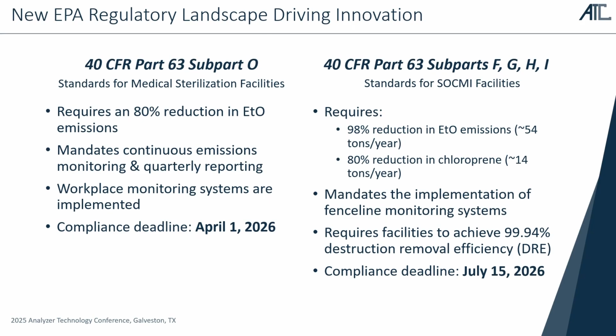So there's three main regulations that came out, and our expected deadline for compliance is sometime around 2026, depending on what the regulation is. Two of them are concerning medical sterilizers, requiring reduction of 80% of ETO, as well as requiring continuous emissions monitoring and workplace monitoring.